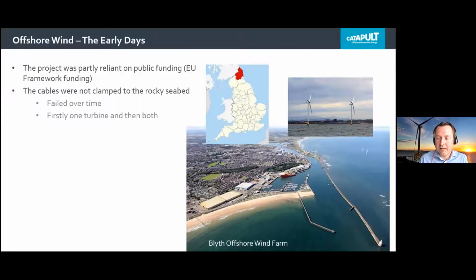This manifested itself in some of the challenges and problems during the life of the turbines. Firstly, I'm assuming due to funding limitations, the cables to shore were not clamped to the seabed, which in that part of the North Sea is very rocky. So probably not totally unexpectedly, the cables failed over time. First the cable between the two turbines failed, taking one out of operation, and that was eventually repaired. Then the cable to shore failed, which meant both turbines were out of operation.